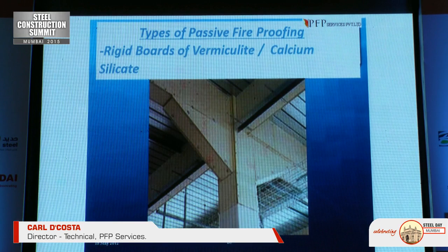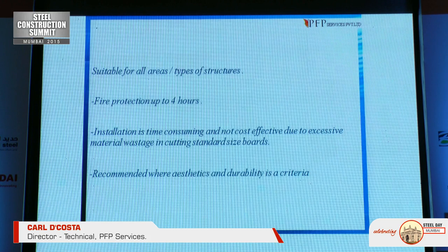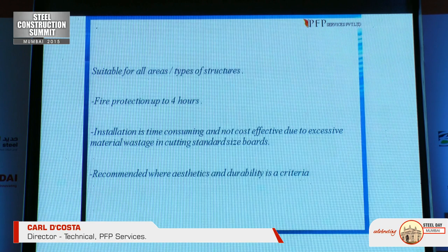The types of fireproofing generally used conventionally: the first type is a rigid board of vermiculite or calcium silicate, suitable for all areas and all types of structures. They can give protection up to four hours depending on thickness, as per fire-rated BS tests. However, installation is time-consuming and not cost-effective due to excessive material wastage in cutting standard-sized boards — wastage can be as high as 50%.